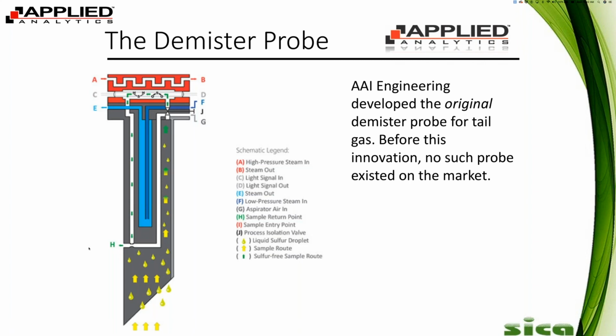And then you can see the sample then continues up into the flow cell, C to D, where there's more steam being brought into the head of the probe, so nothing condenses. Mainly here, we don't want moisture to condense because that can get on the lenses, which will affect the measurement. And the sample then flows down the other side of the probe body where it hits a junction where there's an aspirator that's constantly motivating flow. And then the sample is just put right back into the process pipe. So that's pretty much what the demister probe is doing.